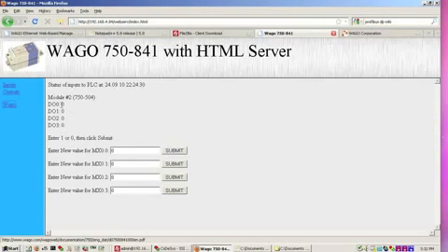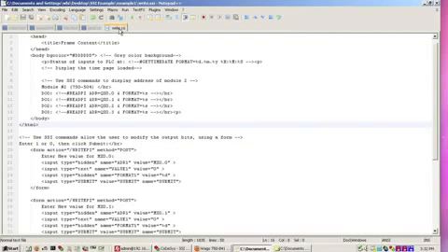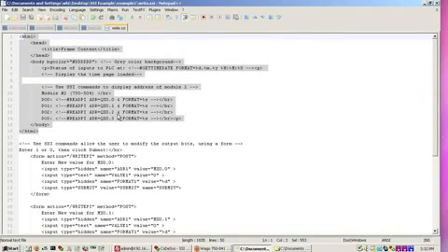So you can see here we've got all zeros. Now in this case we're pointing to a digital address. We could point this to a word if we wanted to bring in a floating point or some counts on a stepper or something like that. You could definitely do that just by changing the addressing and changing the formatting. The write SSI is the same up top. The only difference is that it's actually pointing to the Q addressing instead of the input registers.